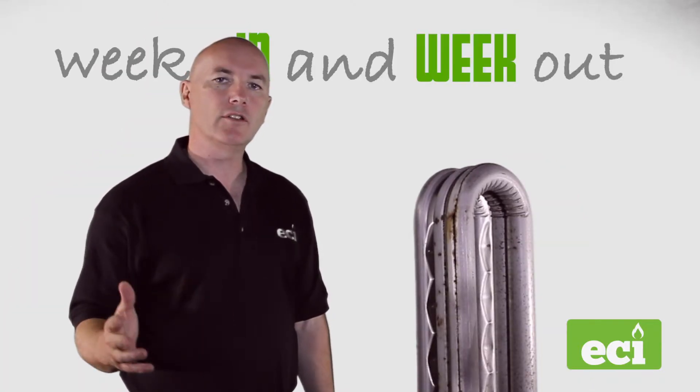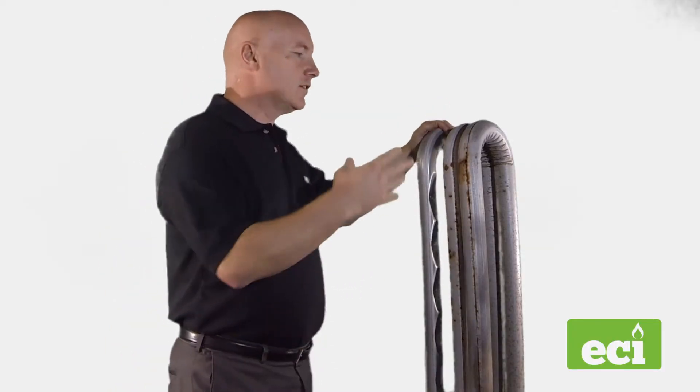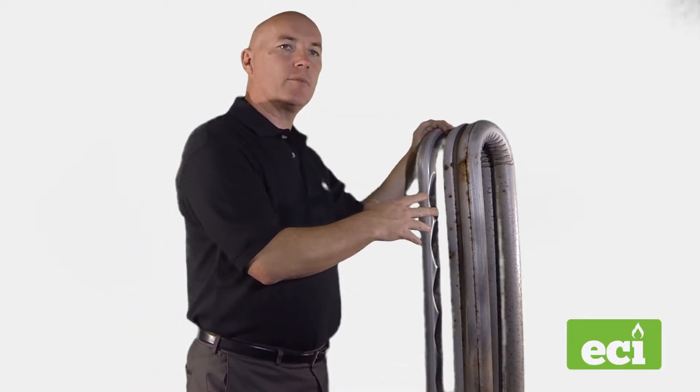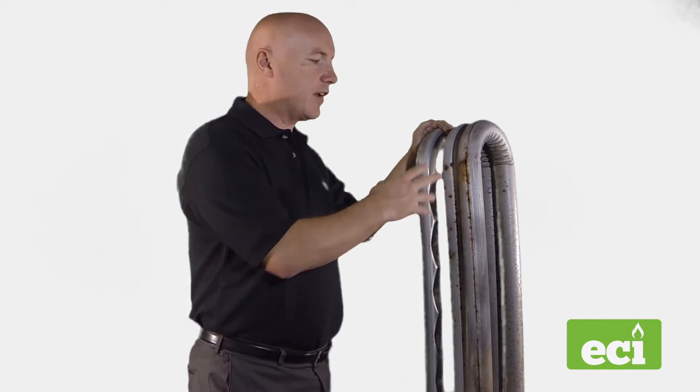This week alone we found two more cracked heat exchangers. We find them week in and week out, and I wanted to bring it to your attention. So what we have here is a commercial heat exchanger. When we were doing the tune-up and safety inspection earlier in the week, we found this crack.